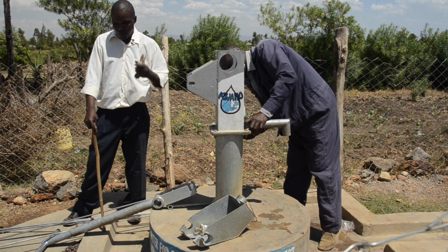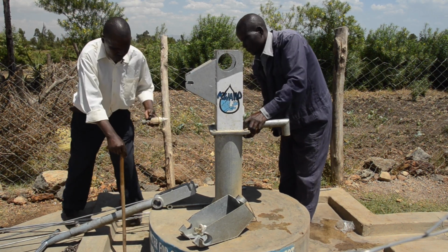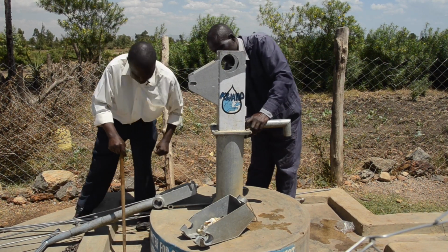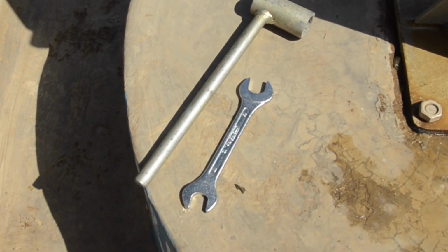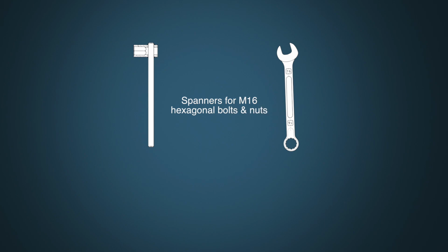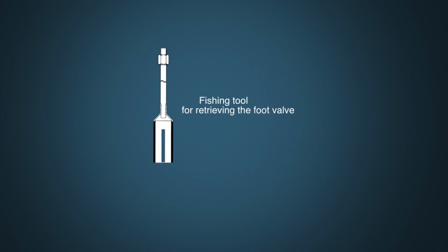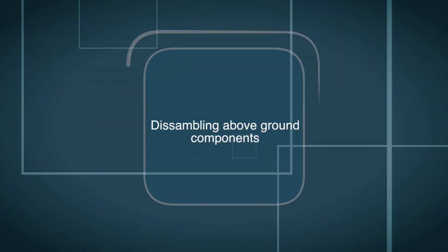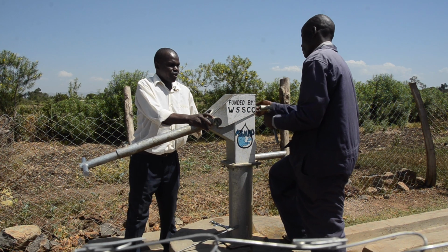When major breakdowns occur, a mechanic may need to disassemble the pump and check each part, in which case the following tools would be needed. 1. A spanner for M16 hexagonal bolts and nuts. 2. A fishing tool for retrieving the foot valve. Procedures to disassemble the above ground components of the pump are as follows.